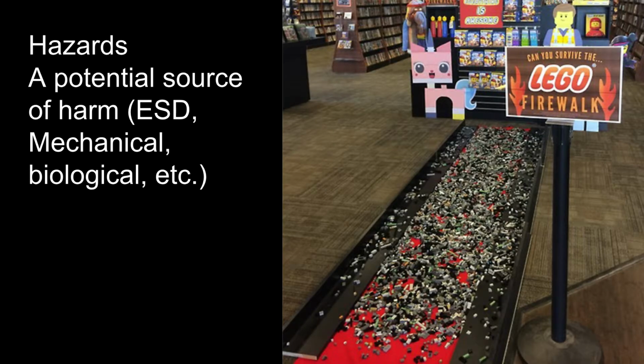So, to refresh yourselves on the terminology of risk analysis, we're going to need a few terms. The first is hazard. A hazard is a potential source of harm. And when we're talking about risk analysis for medical devices, usually this is like broad categories. So think like biological harm or mechanical energy or electrostatic discharge or electrical harm, these sorts of things. And I'll show you what that looks like in Greenlight in a moment when we get there.